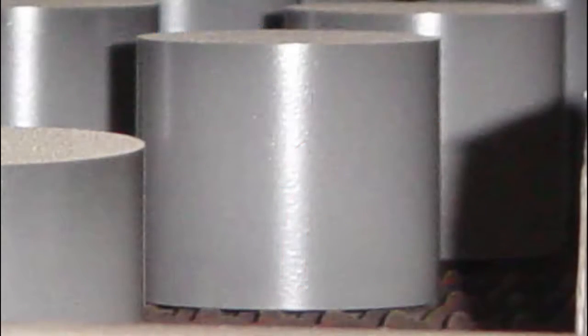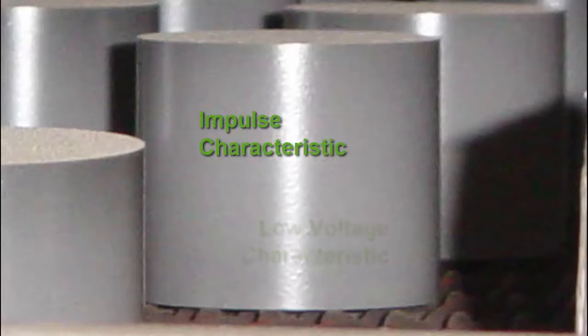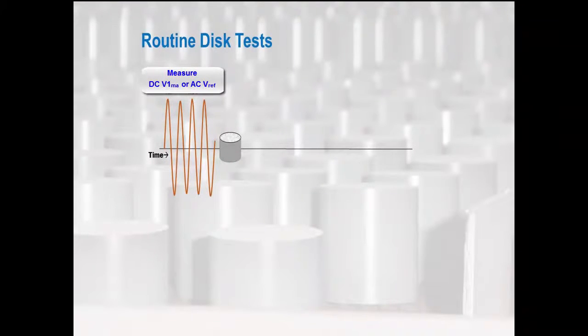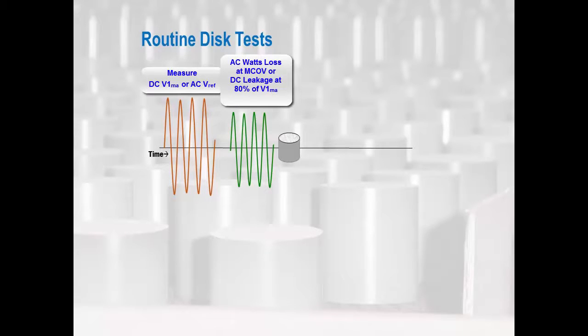A good quality disk always comes with thorough characterization. This characterization comes with a measurement of its impulse characteristic and its low voltage characteristic. This is a characterization of every disk manufactured and is necessary to guarantee the characteristics of a good quality arrestor. The first step in this characterization is an AC or DC test that measures the turn-on point of a disk. This turn-on characteristic is referred to as its V1MA or its reference voltage. Either test works quite well. The second step of its routine characterization is to measure its leakage current. Monitoring the leakage current at or near its operating voltage guarantees the arrestor will not exceed its published watts loss.